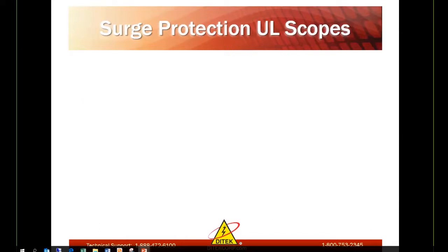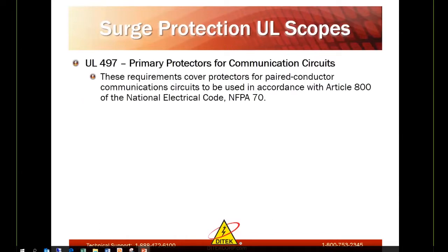Surge protection UL scopes. UL 497 is a listing for primary protectors for communication circuits. These cover protectors for paired conductor communication circuits to be used in accordance with Article 800 of the NEC, NFPA 70.